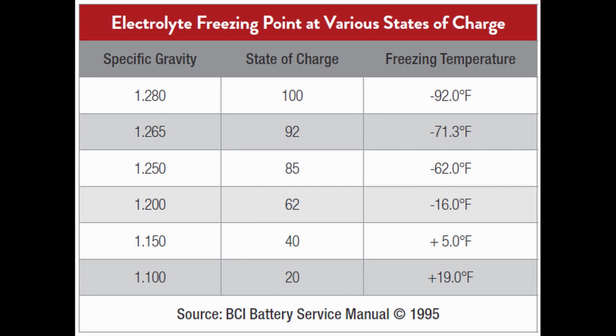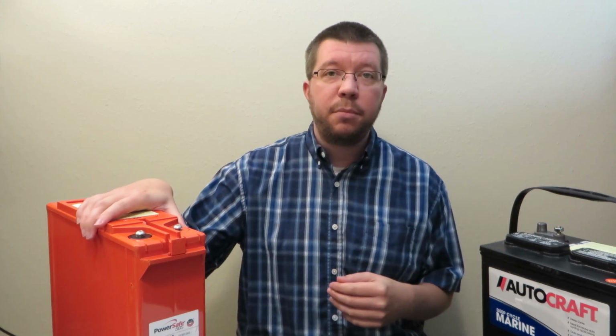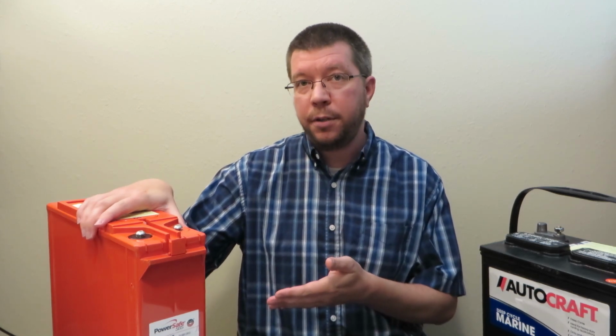Note this chart if you live in cold climates and the batteries are exposed to the elements such as in an RV. In that case, you might want to stay above 50% state of charge, only to prevent the batteries from freezing down to temperatures of about -20°C or -5 Fahrenheit. Lead-acid batteries do freeze. AGM batteries can handle it better, but you still don't want to intentionally freeze them.